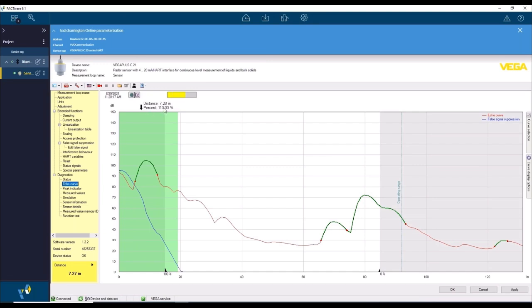This system is already spiked. We have more than the normal amount of buildup that you will have on the sensor. We got actual over an inch or two of buildup we packed on that antenna just for this training class. So what has happened is that the sensor is now spiked to the buildup off the antenna. So now here we go. This is your fix. Now note that the gauge is currently in an upset mode.